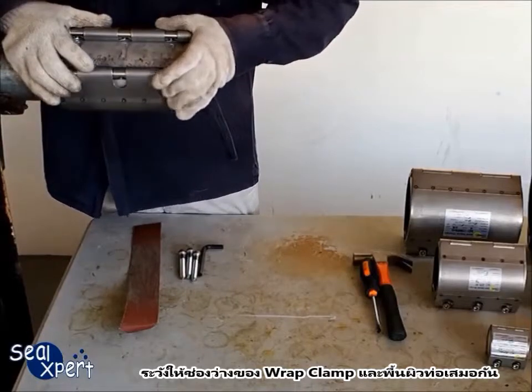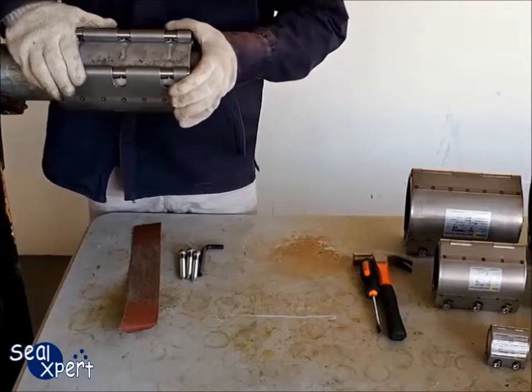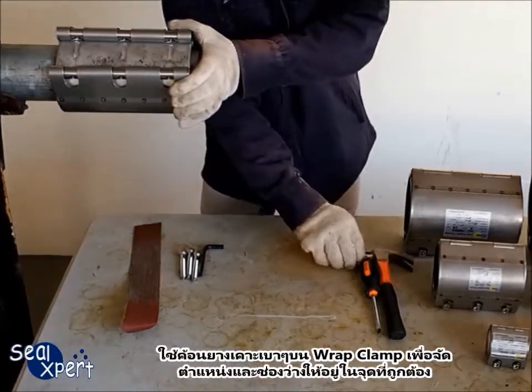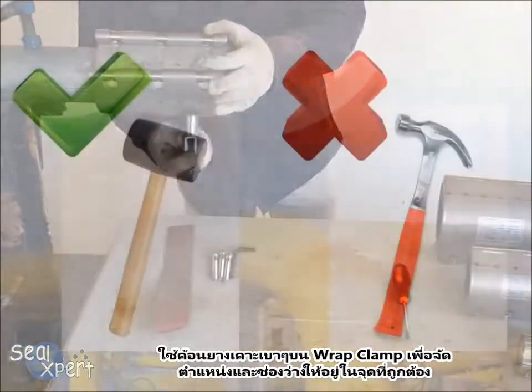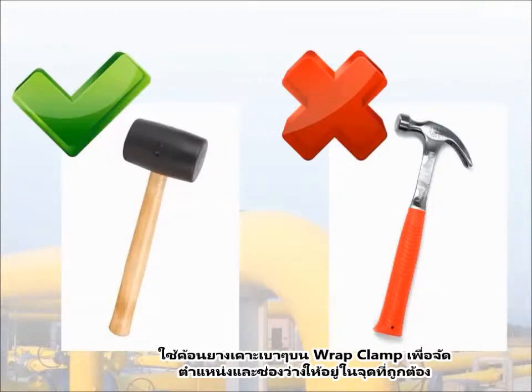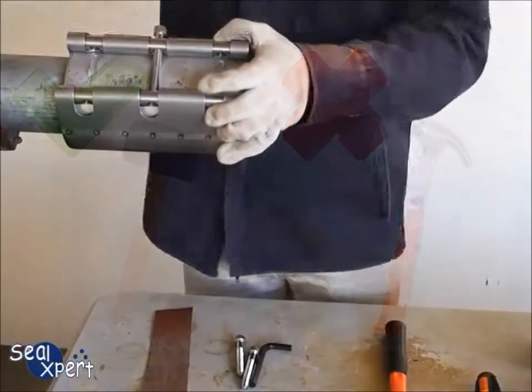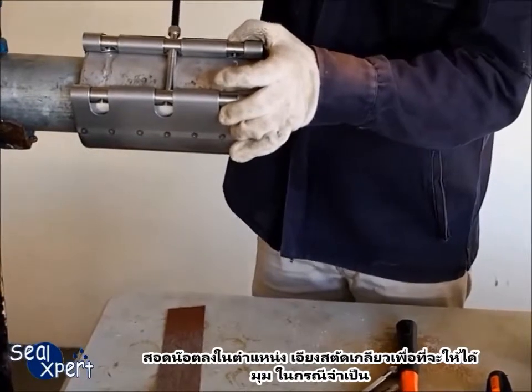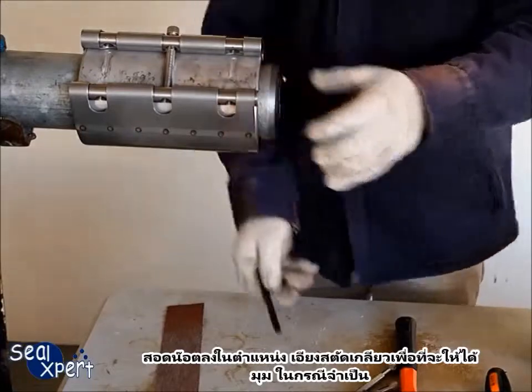Ensure that the gap between the Wrap Clamp and the pipe surface is even. Use a mallet to gently knock the Wrap Clamp into position and ensure all tabs are fitted correctly. Do not use a hammer as this may deform the Wrap Clamp. Slot the bolts into position, and tilt the threaded rod to accommodate the angle of bolts if necessary.